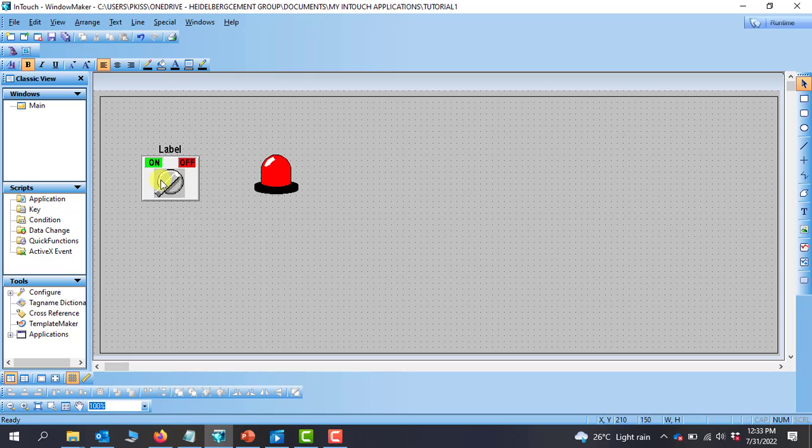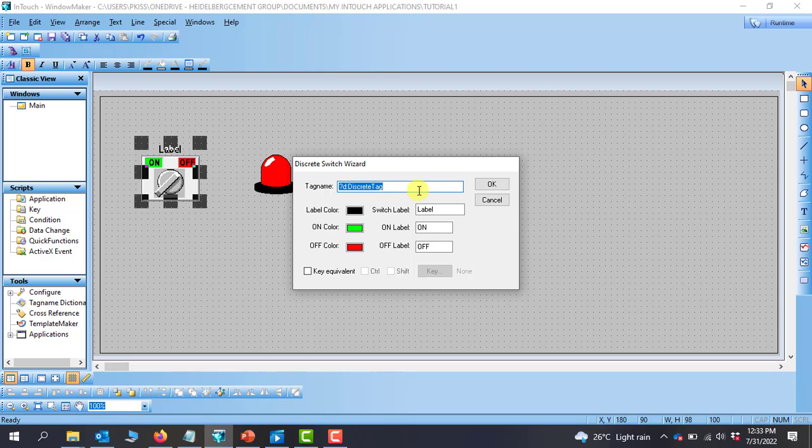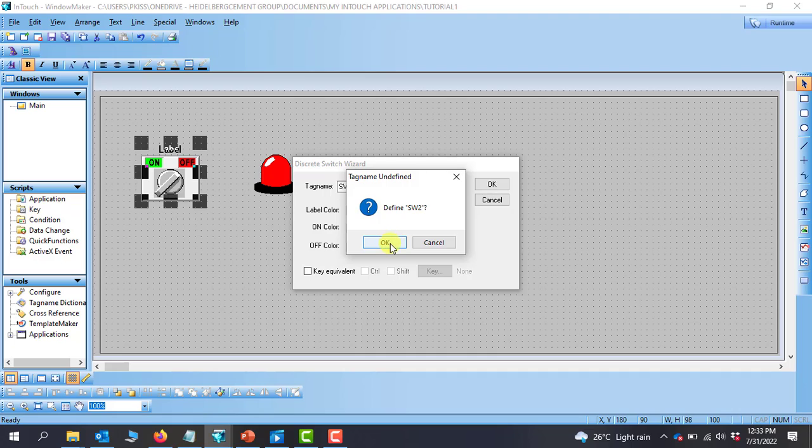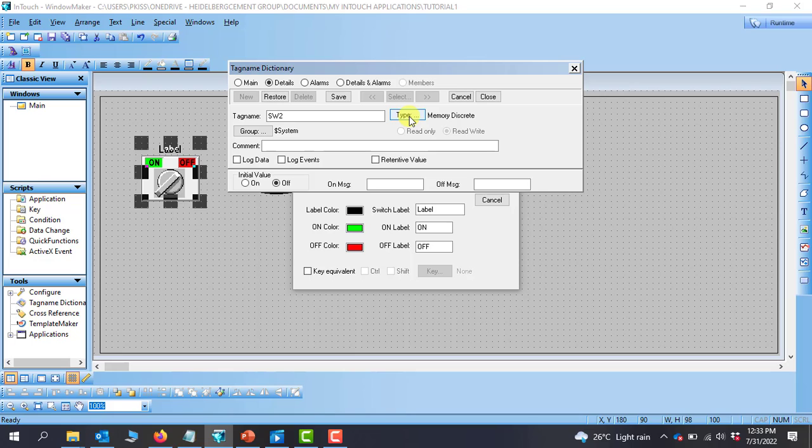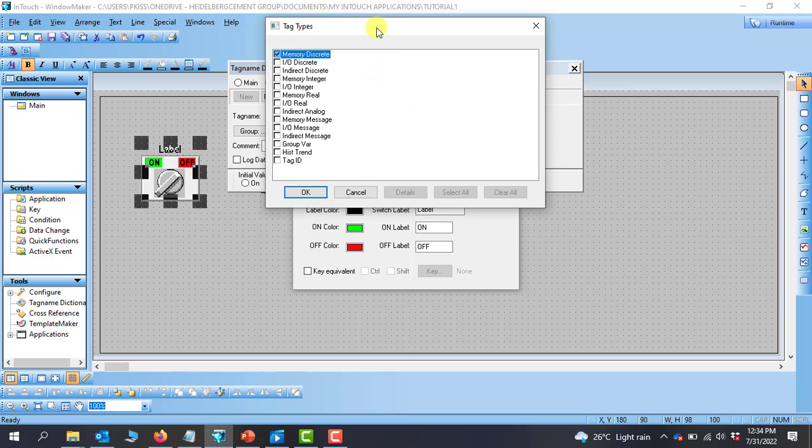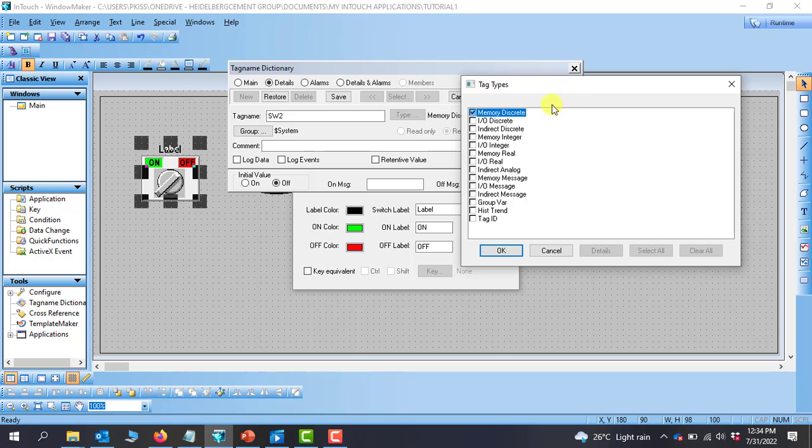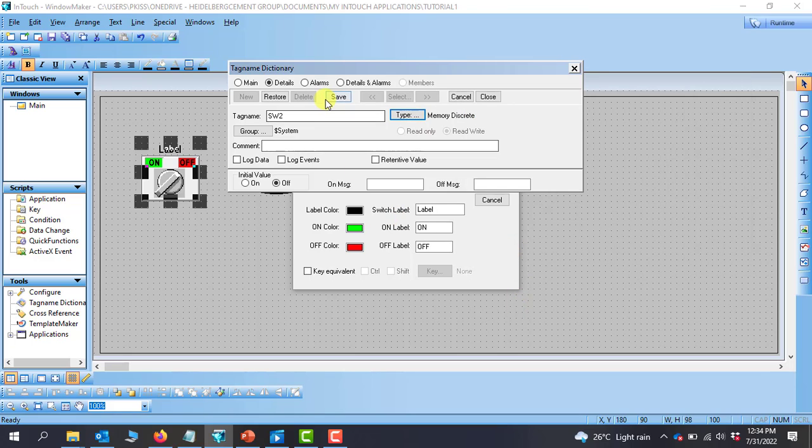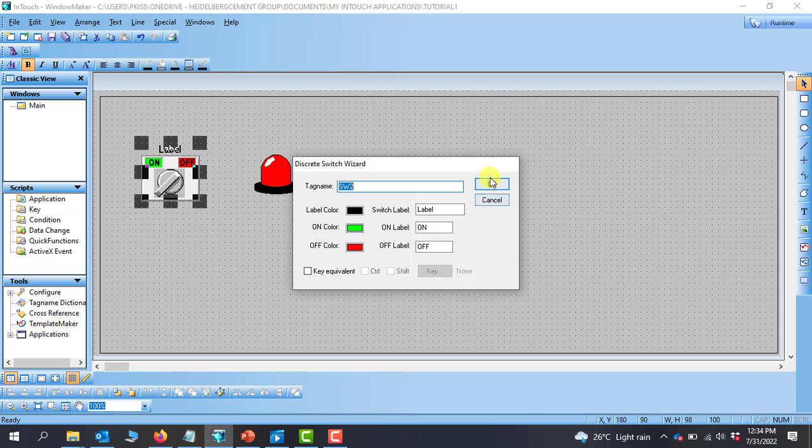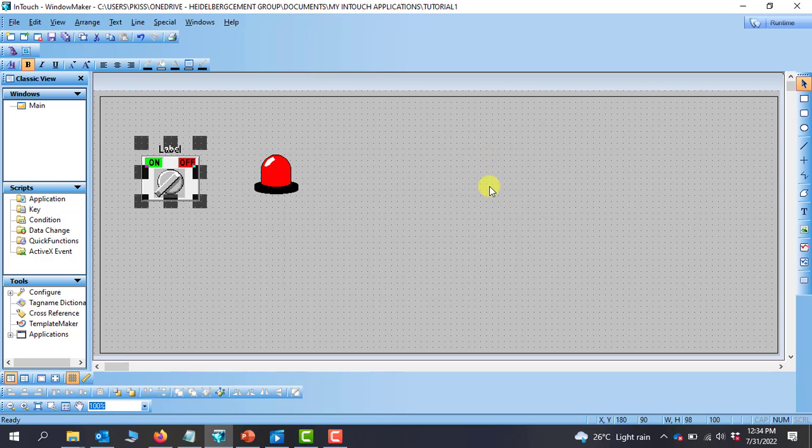Okay, so we have our border lines. Now we have our switch, we have our lamp. When we have our lamp, the next thing to do is to create tags for them. So we can double-click on this one and call this one switch two. We need to choose the type because this is a digital unit. We need to choose discrete, and basically in the previous tutorial I explained why we choose memory discrete, not IO discrete. So we select memory discrete and then click on save.